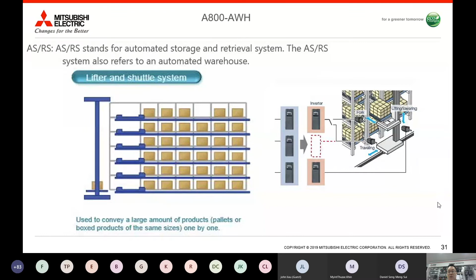Next, on regenerative solutions. If you look at this picture, you may wonder how the inverter can save energy when it is decelerating. We have a saving solution called power regen solution. Basically, when the inverter is decelerating, the motor is actually acting as a generator.